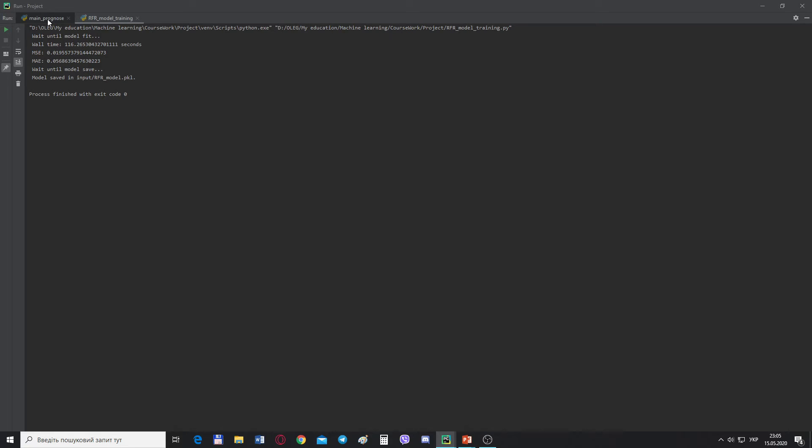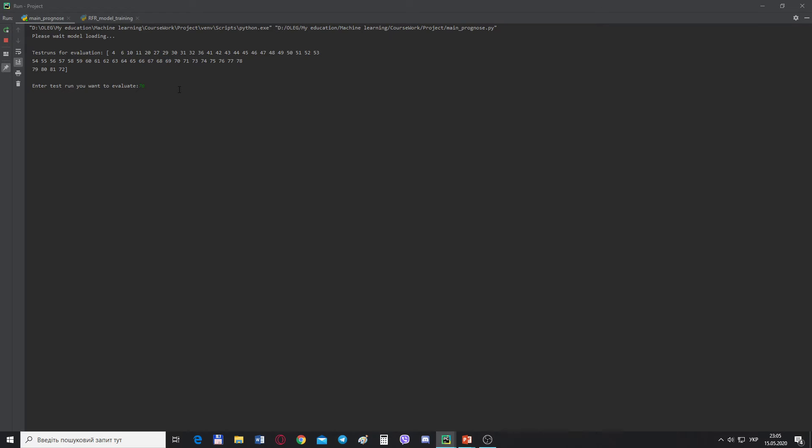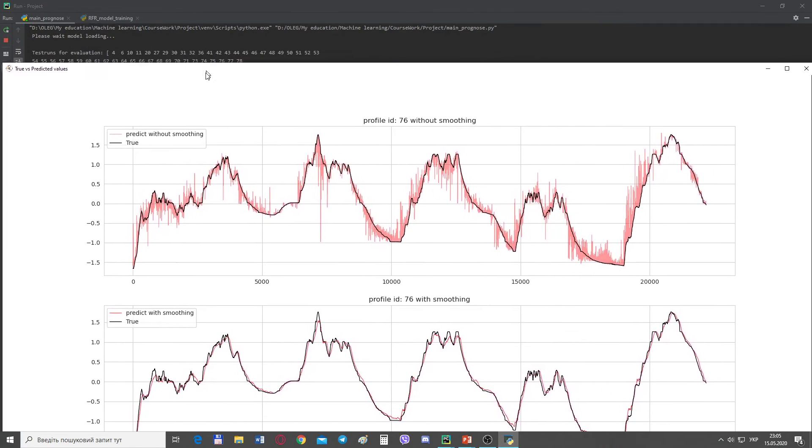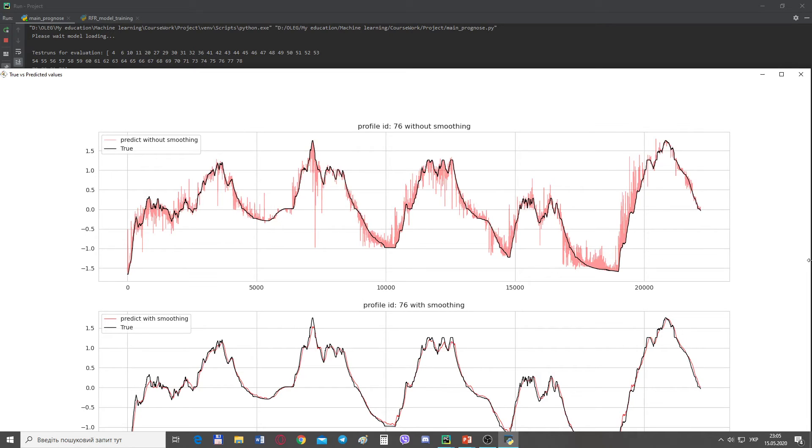Now I'm running the main prognosis program and wait until model is loading. Model loaded. After the model is loaded, I need to enter the value of the test cycle. The top graph shows the true stator winding temperature in comparison to the values predicted by the random forest regressor. As we can see, the random forest regressor seems to be able to capture the global trends in the stator winding value, but still there is a lot of noise in the predicted values.